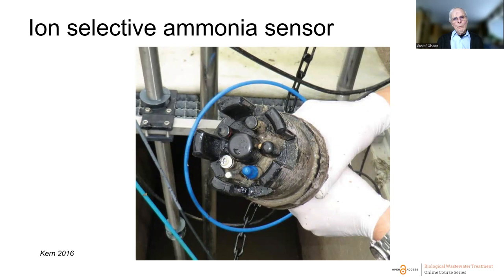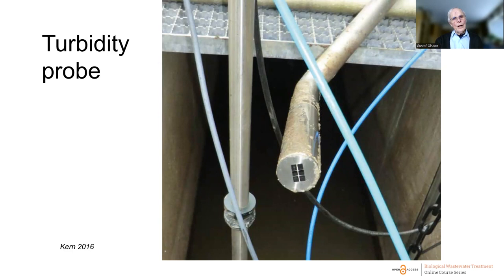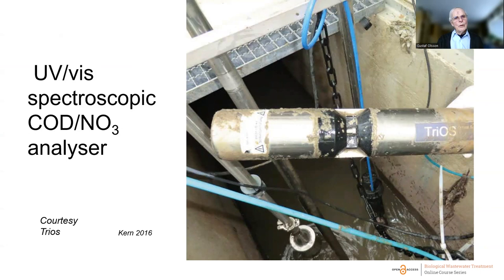An ammonia sensor is an ion-selective sensor containing interesting sensing elements, and it is considered an advanced sensor giving useful information. A turbidity probe can also provide important information about suspended solids in various parts of the process. A COD or nitrate analyzer is built on UV spectroscopic analysis to determine the amount of organic pollutants.